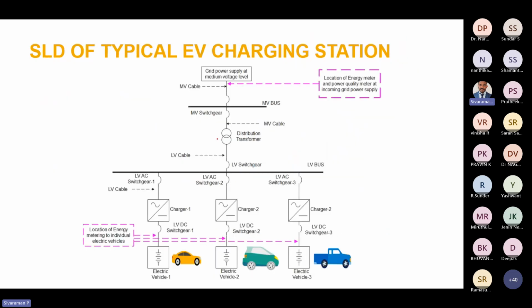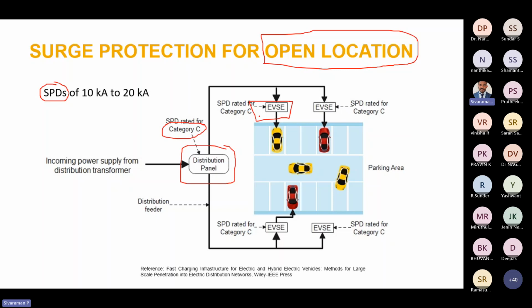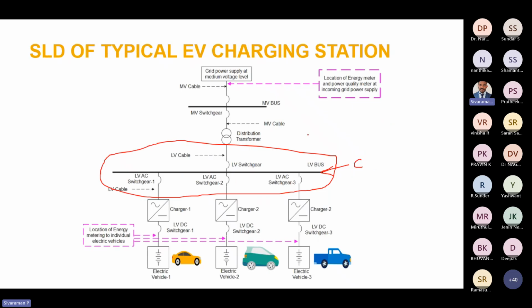In this example, this is the main distribution panel where we use Category C, and the EVSE, that is the supply equipment or charger, also requires Category C at those locations. So however many chargers we have, that many such protective devices we have to use. In this example we have three chargers, so for all three we have to use one Category C SPD each, to prevent these equipments from direct lightning stroke.